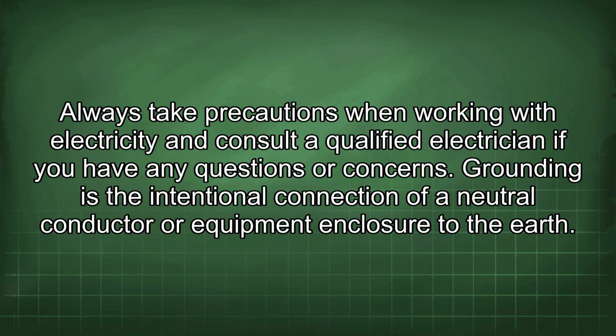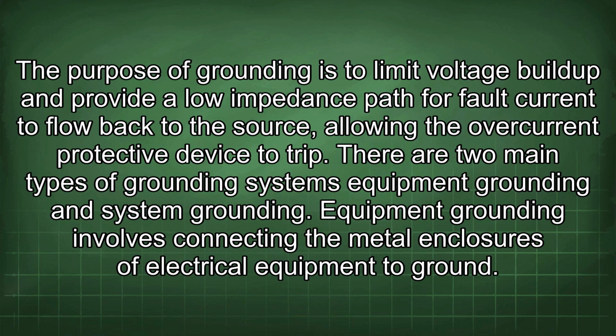Grounding is the intentional connection of a neutral conductor or equipment enclosure to the earth. The purpose of grounding is to limit voltage buildup and provide a low impedance path for fault current to flow back to the source, allowing the overcurrent protective device to trip. There are two main types of grounding systems: equipment grounding and system grounding.